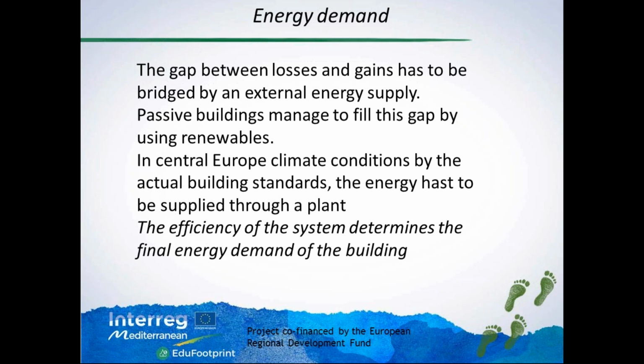By the way, if we first reduce the energy losses by integrating an insulation, we have the possibility to also reduce the size of the energy plant, or the generator. So we have a double economic impact, because we have a bigger savings effect, but afterwards the expenses for the change of the heater are lower because we have to choose a smaller heater.